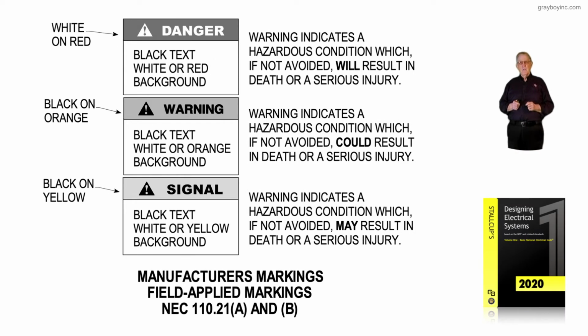Now this illustration deals with field marking in accordance with NEC 110.21(A). Notice there's a label there in orange. The label is installed per 110.16(A) and (B).